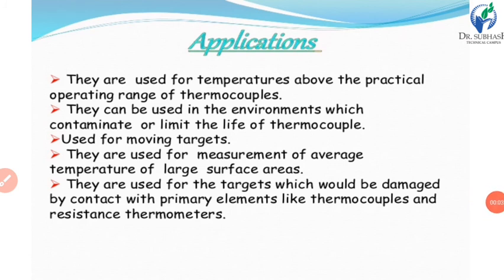Now we will see the applications of pyrometer. So pyrometers are used for temperatures above the practical operating range of thermocouples. It means whenever the temperature range is very high, at that time we can use a pyrometer because it is a non-contact type device. They can be used in environments which contaminate or limit the life of a thermocouple. It means in some environments the thermocouple life is reduced due to the atmosphere or other parameters, nearby objects.